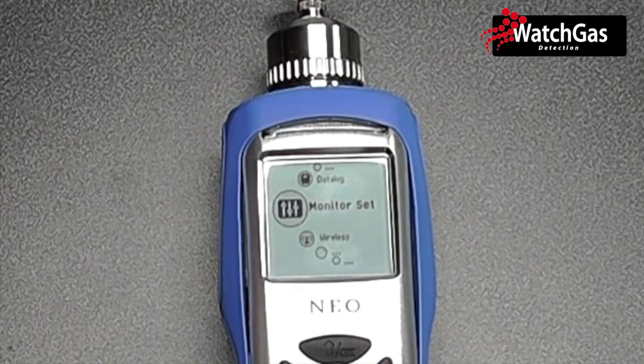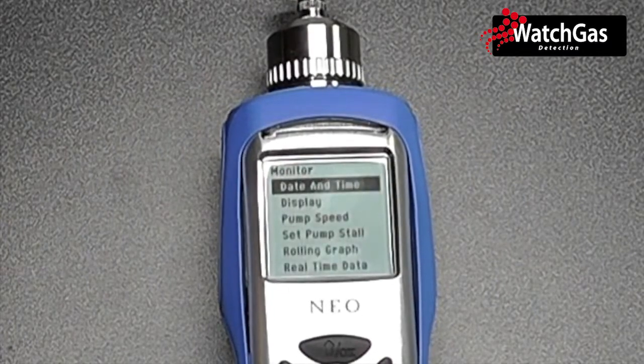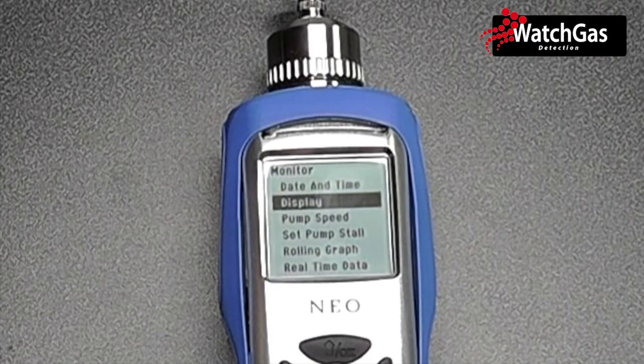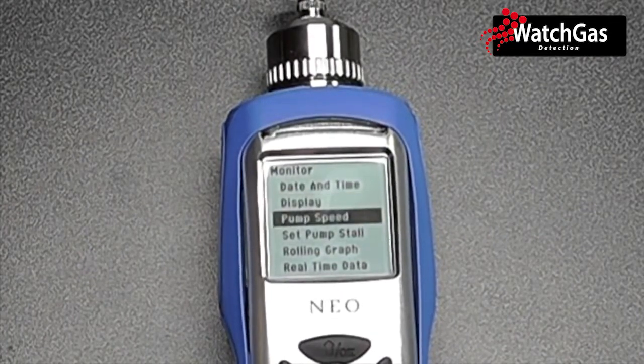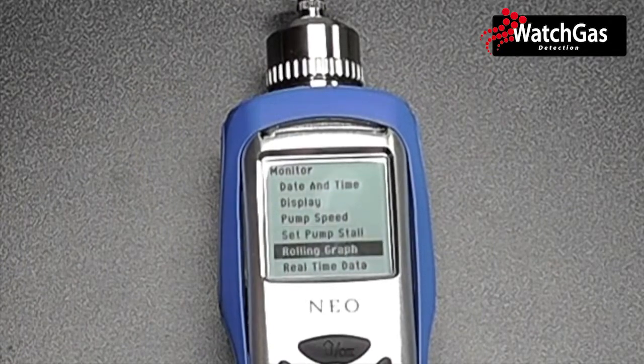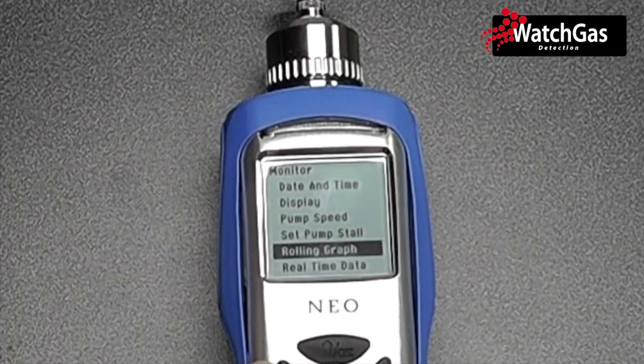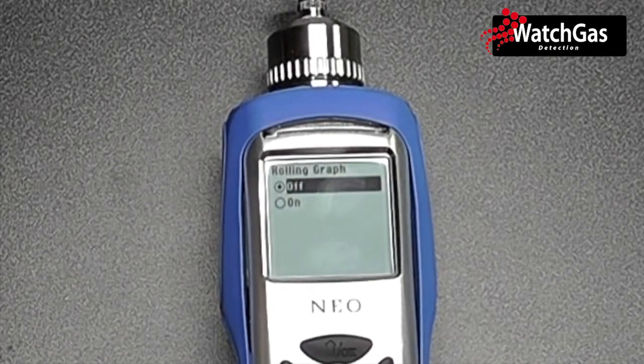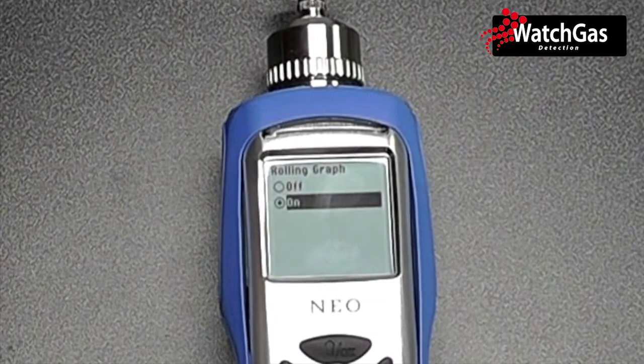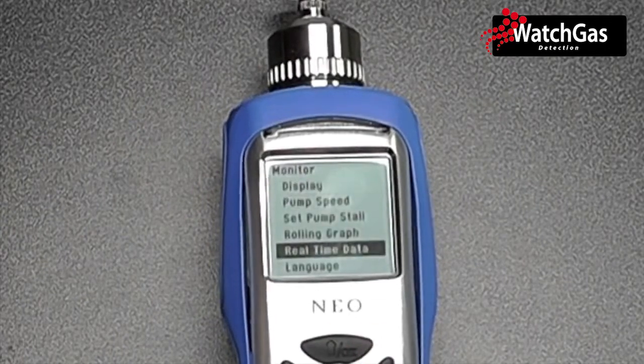We can look at the general monitor setup, so changing date and time, any display settings like brightness or contrast, changing the pump speed, setting the pump stall rate. We have an option for enabling a rolling graph rather than just a direct reading on the screen, which I will enable so you can have a look at what that looks like. So to enable the rolling graph, turn it on, and then it can come back out.